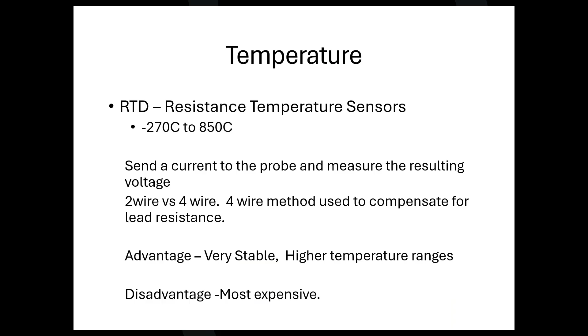An RTD is very accurate, and it works similar to what we call a 4-wire resistance, where I'll take something and put a current in on 2 leads, with 2 separate leads to measure it coming back, so that the current I'm injecting isn't taken into effect or causing a problem. It's just a more accurate way of doing things that we have to do sometimes. That's for something that you need to be extremely accurate, but it's going to be expensive to you.